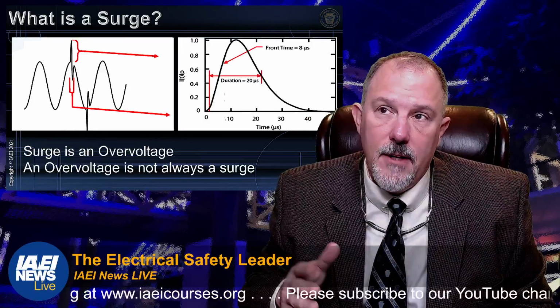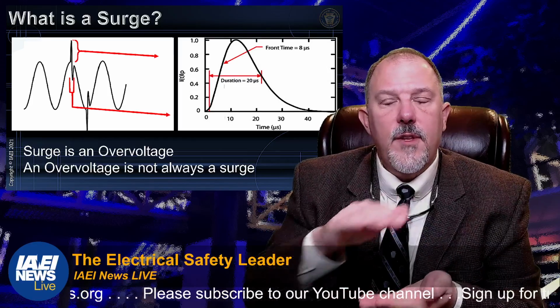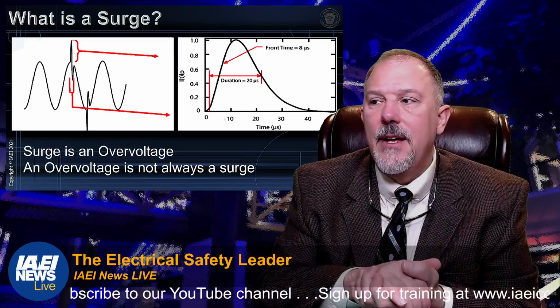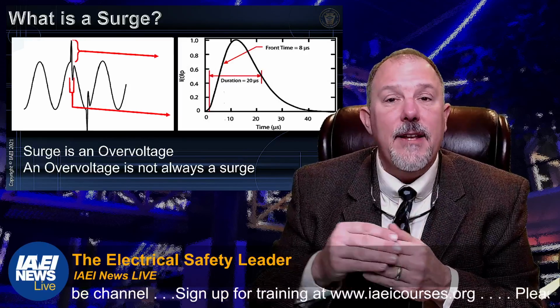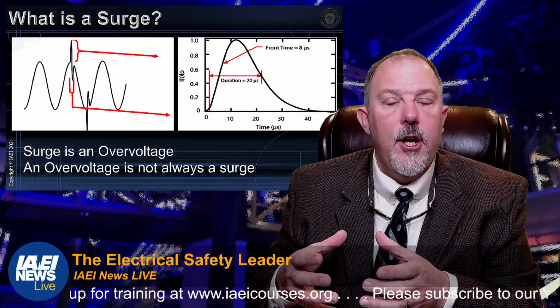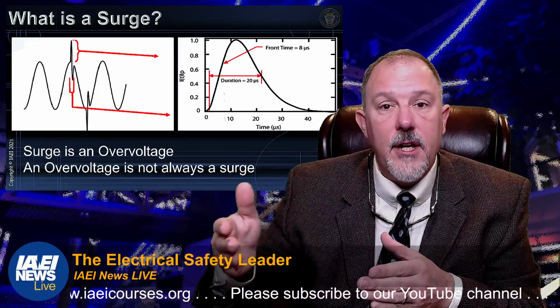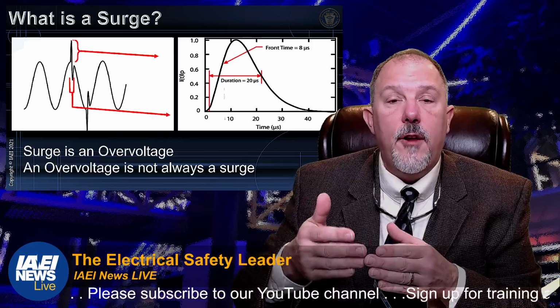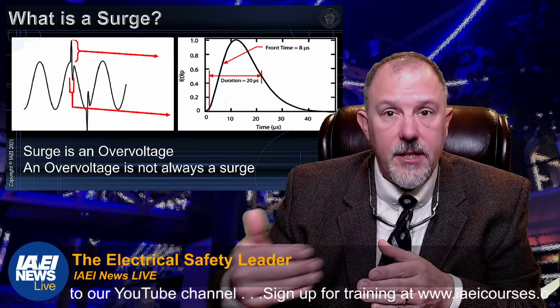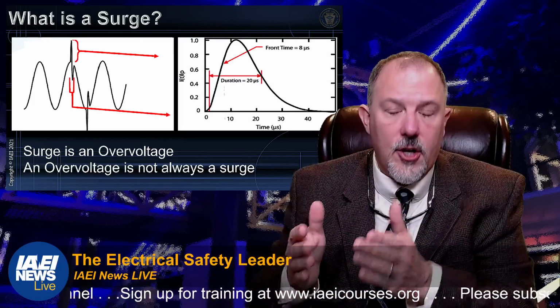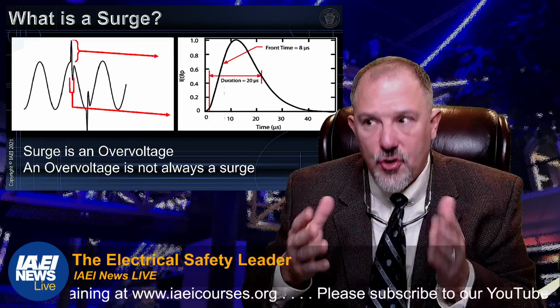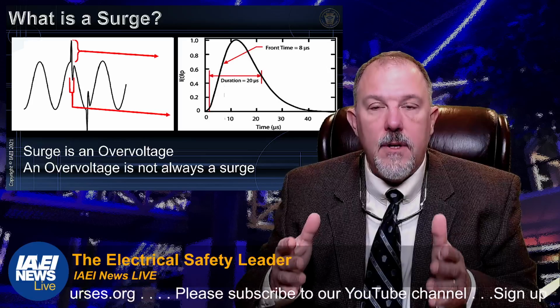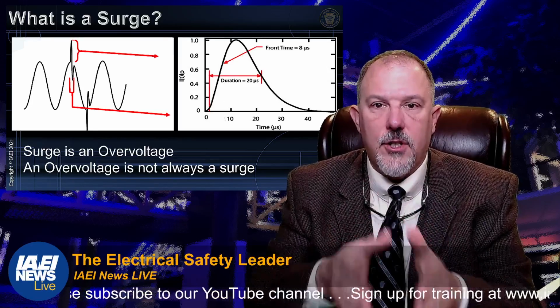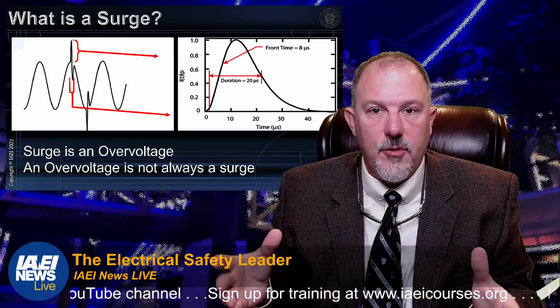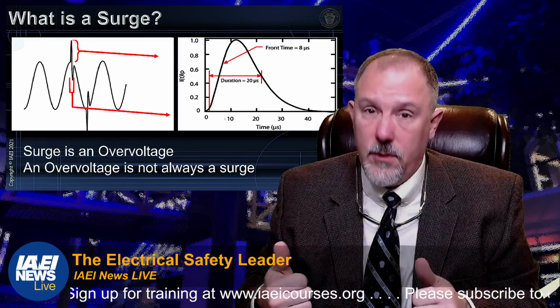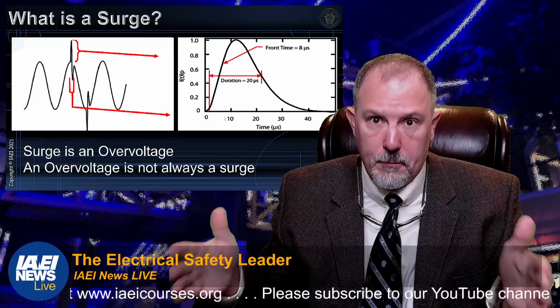So, a current event. We get into a lot of this discussion. This discussion, when we talk voltage impact and current impact, is typically like a power quality discussion. In some cases, you might have harmonic content. You might have events that impact current to a specific load. I could have a harmonic distortion on current going to a drive, and that's current distortion. Now, you could make the argument that a current distortion will impact the voltage, which then impacts a broader range. True, that's true. But a current distortion driven by a load will impact that branch circuit itself more so than the entire distribution system.